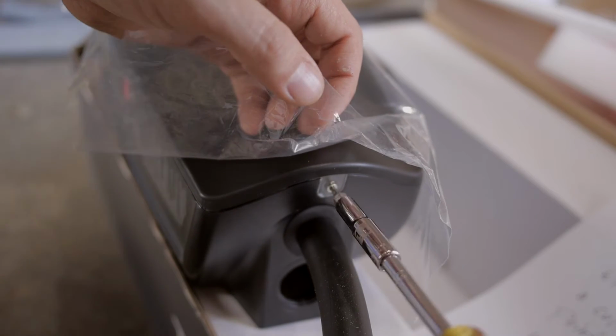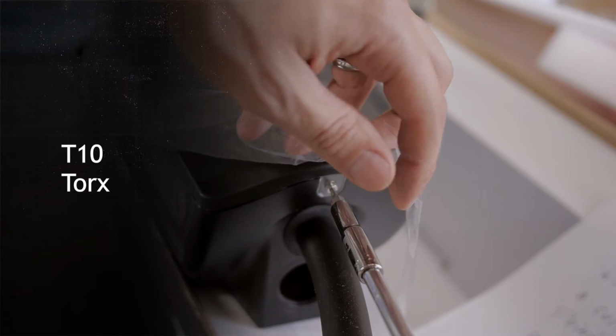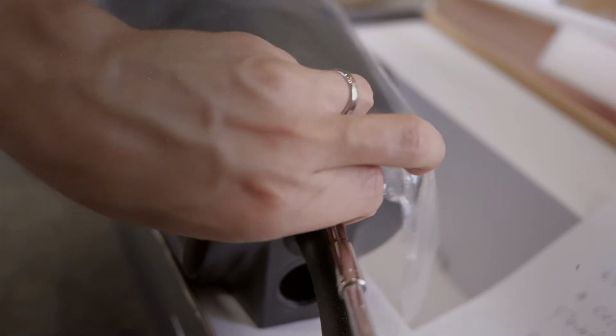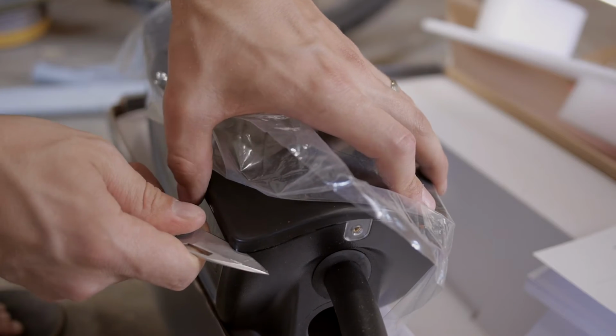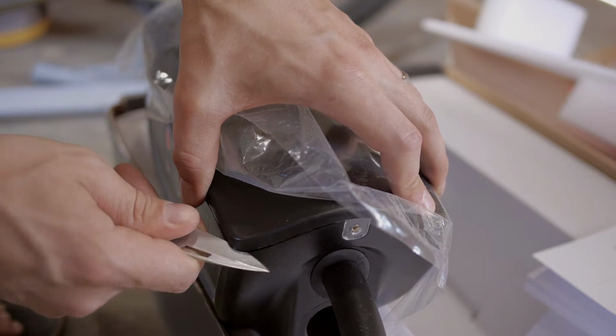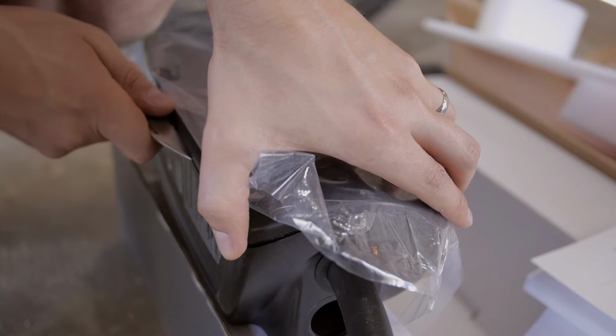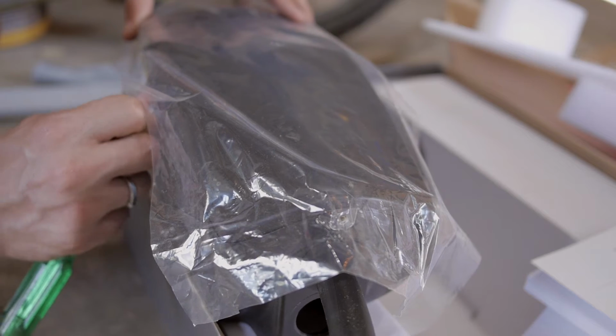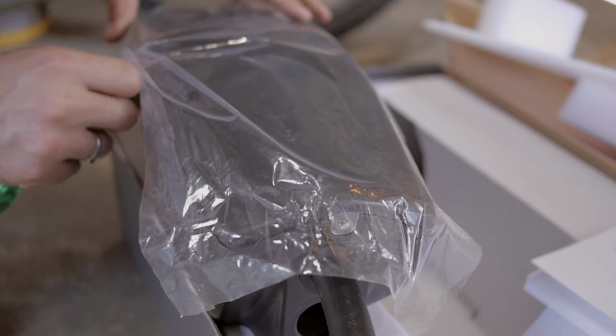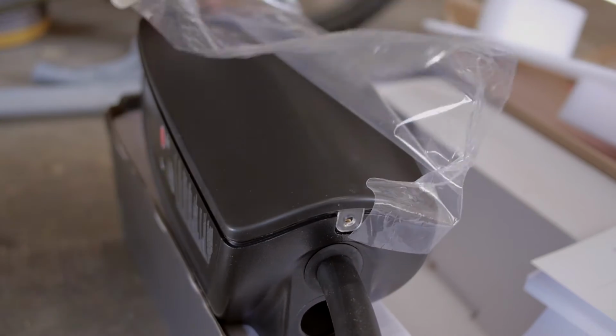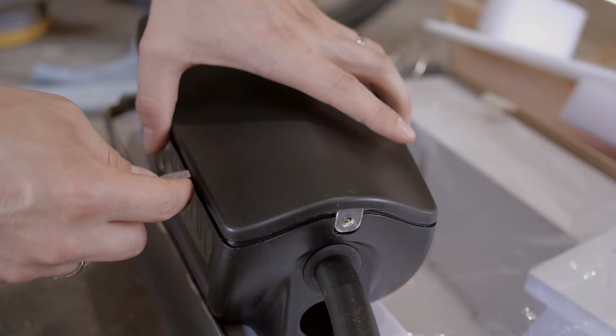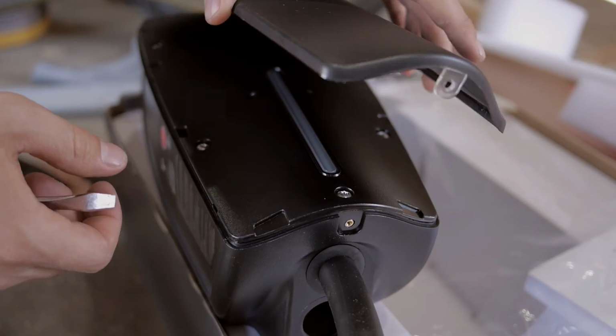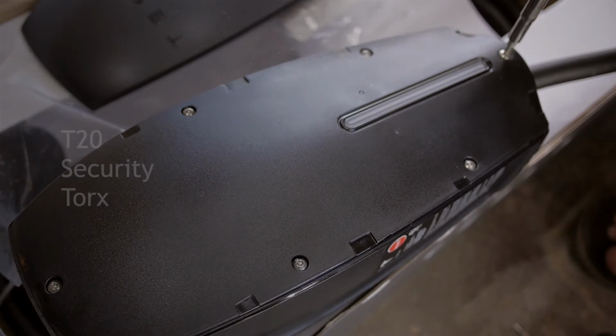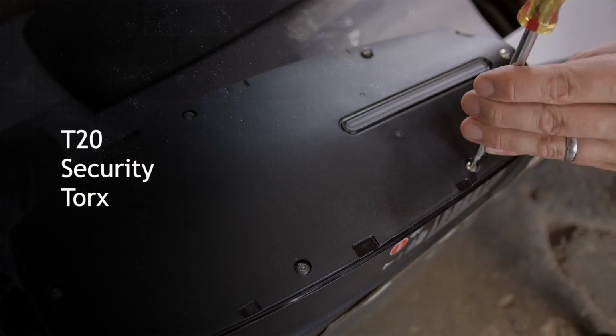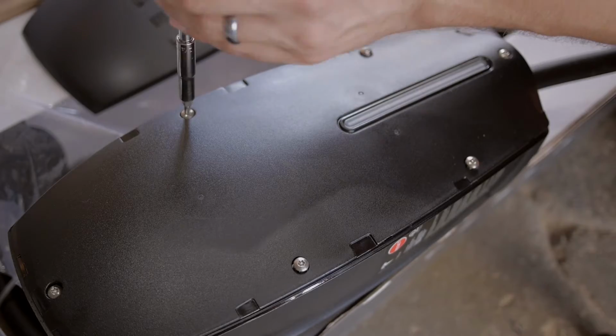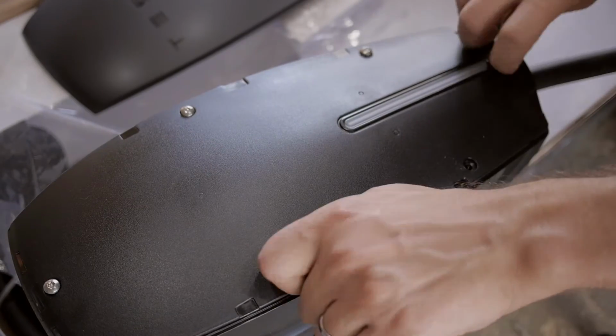With the base plate mounted, the next step is to remove the T10 Torx screw at the bottom of the charger's front cover. Then you slowly and very carefully pop loose the clips all around the front cover. I started on one side and began to work the cover loose there, and then worked around the cover, being very careful not to damage it. Eventually it let loose though, and I was able to get to the weathertight cover underneath. There are 6 T20 security Torx screws that you have to remove from this cover.